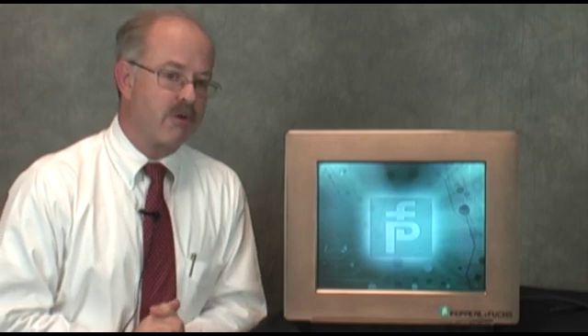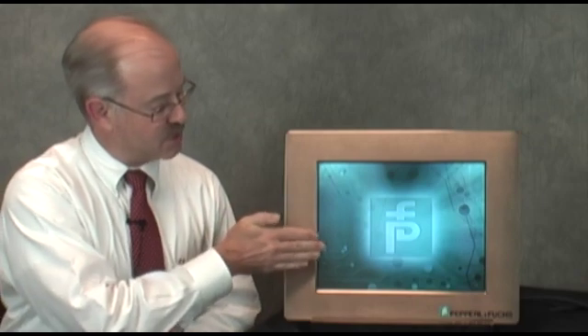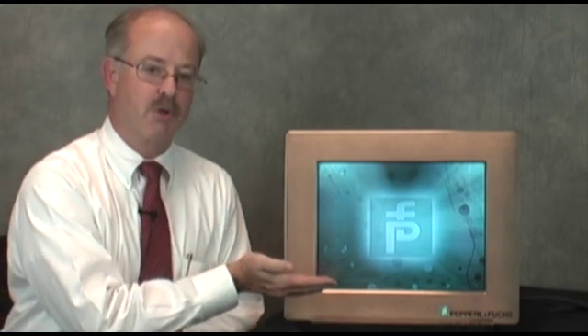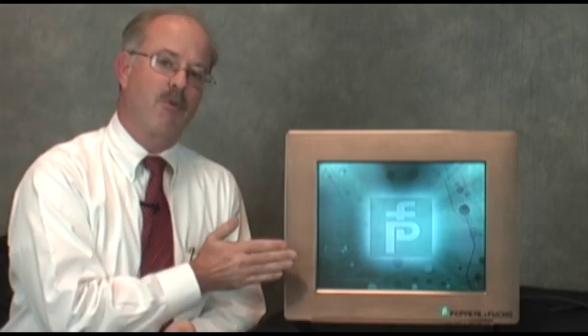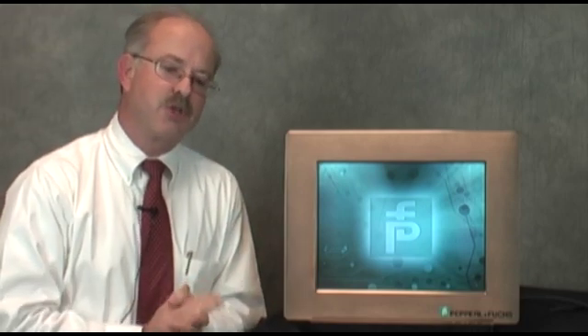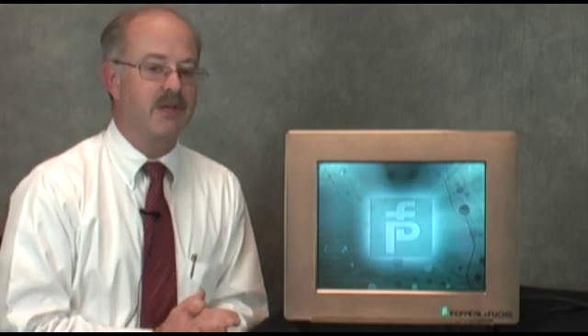Further, a much wider viewing cone both in the horizontal as well as in the vertical, and very importantly true color through that entire viewing cone. An industrial grade LCD even from the most steep angle red is still red, blue is still blue, and of course green is still green. Whereas with a consumer panel we tend to get color shift as we move off angle. If we're doing an Excel spreadsheet at home at night that's no big deal, but in process control things like red and green mean things that are process critical, so we truly want to see those colors.